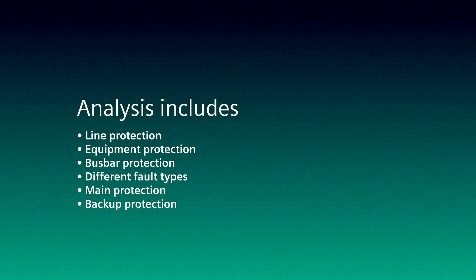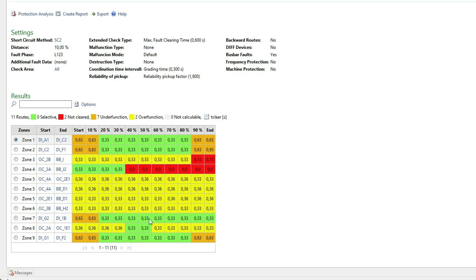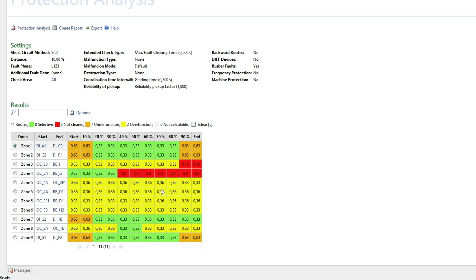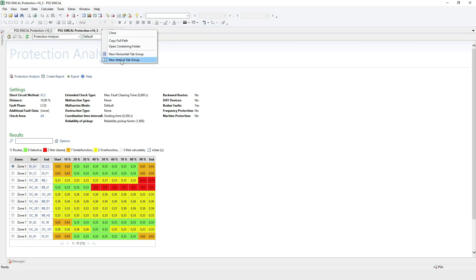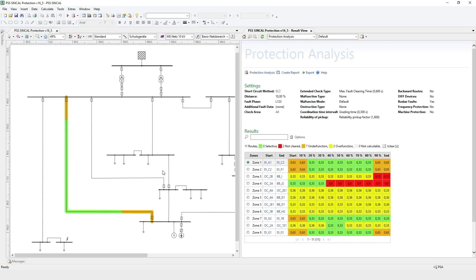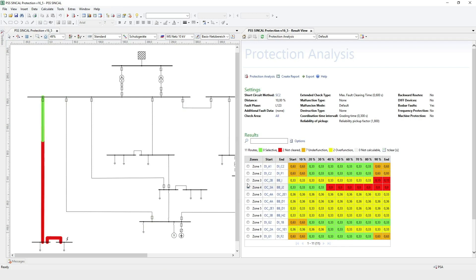With the Protection Analysis function, you get a fully automated check of your protection system for your entire network. During the analysis, fault events along every protection area are automatically calculated and the protection behavior is evaluated. The analysis finds weak points and highlights them in a result matrix, showing whether the protection system was able to clear a fault, and making you aware of unwanted or failed operations. For a more visual representation, the corresponding protection areas can be highlighted in a network graphic, and protection simulations for specific fault events can be performed directly from the result matrix.